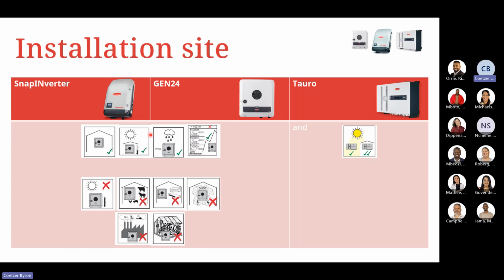When you are doing the installation on site, the Snap inverters and Gen24 can be installed indoors, in a shaded environment. We do not recommend that the units are installed in direct sunlight. This is just due to the heat sinks. The Snap inverters have the heat sink on the back of the unit, but it is still heavily affected by heat soak.